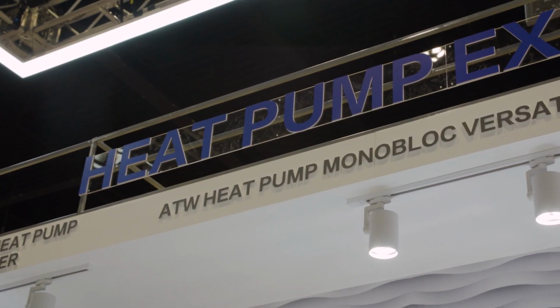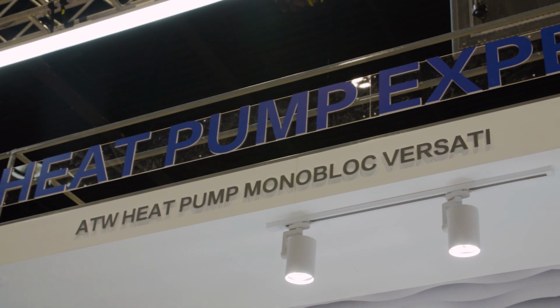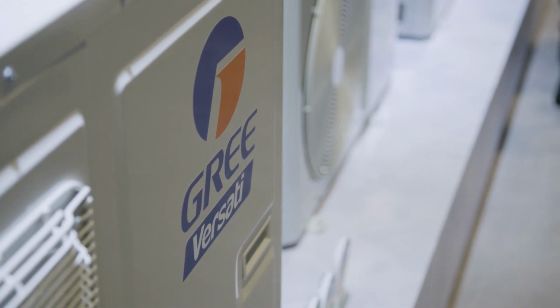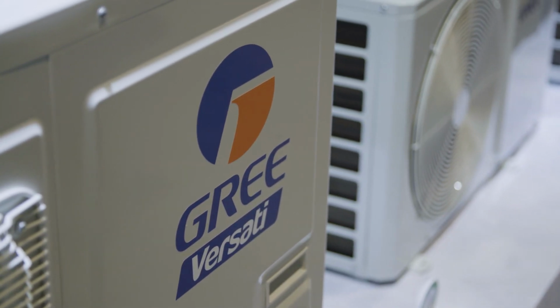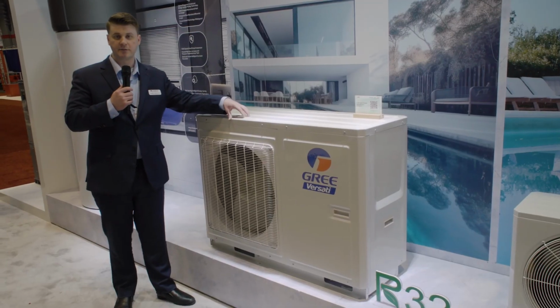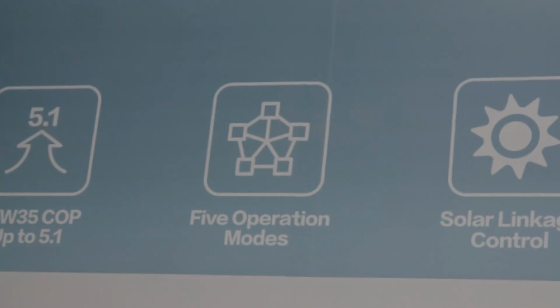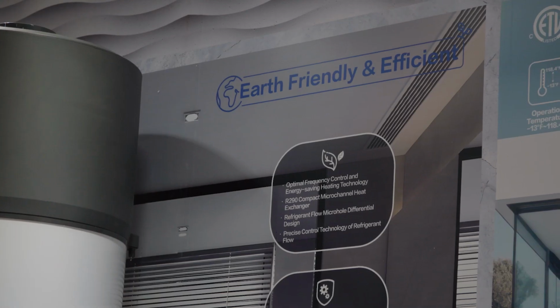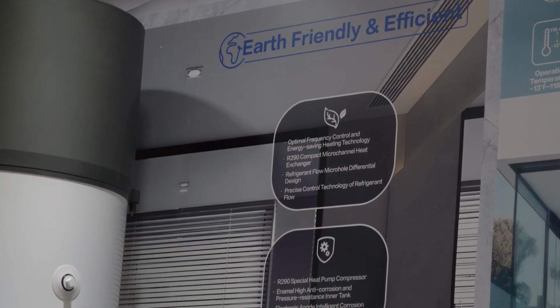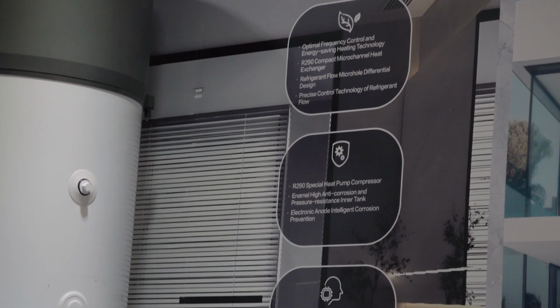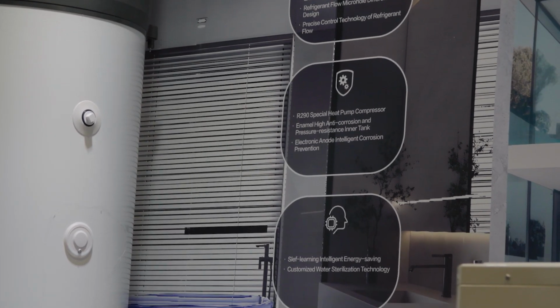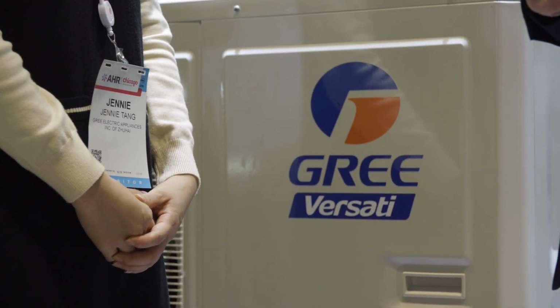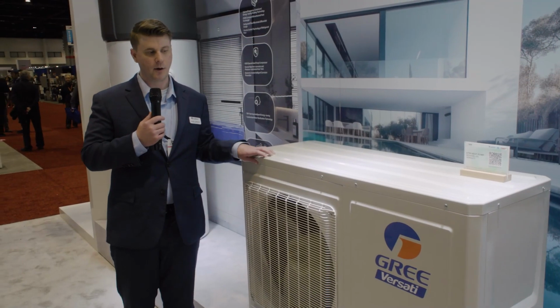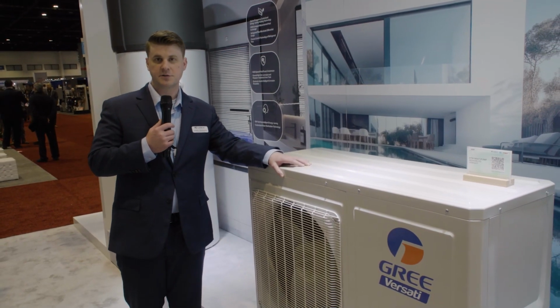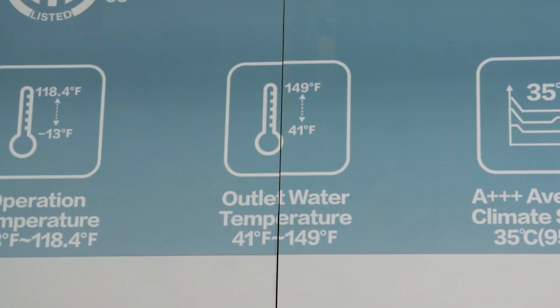We call it a monoblock because all of the refrigerant exchange is done in the outdoor unit. You don't need to install a separate hydro box inside, so it makes it much more convenient to install. The system has 5 great modes. You can do space heating and cooling with hydronic fan coils, radiant in-floor heating, domestic hot water, or space heating or cooling plus domestic hot water. Discharge temps on this get up to 149 degrees Fahrenheit.